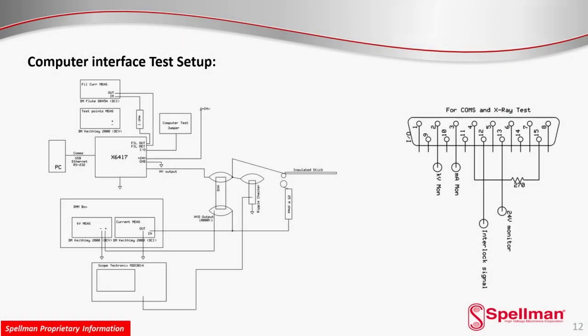The next step is to perform the computer interface test. The computer interface test verifies the operation of the Micro X6417 with the serial, USB, and Ethernet interfaces through the Spellman GUI. In order to perform this communication, the computer is connected through these interfaces, while the fixture that was connected to the 15-pin connector is replaced by a jumper that contains only the interlock setting and kV monitor signals that will be reviewed during the test.